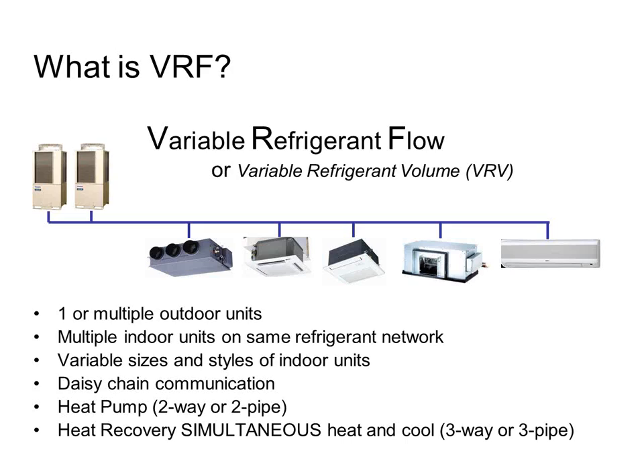All these types of systems from all of the manufacturers have built-in controls to them. Right, so every single indoor unit has its own control system built into it. All the outdoor units have their own control systems, and they all use proprietary communication to send data between the indoor and outdoor stuff. So you cannot mix and match brands. You can't put manufacturer A's indoor stuff on manufacturer B's outdoor stuff and vice versa. You also cannot use your own third-party control systems. You can have third-party controls integrate to these, but you can't gut them and put your own controls in, at least not within the warranty.